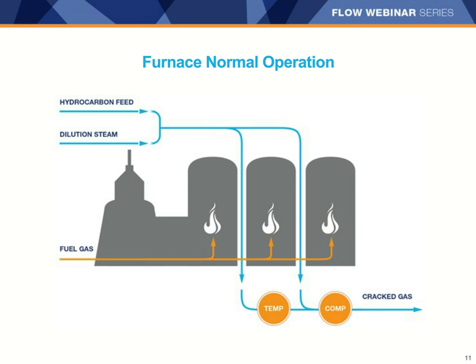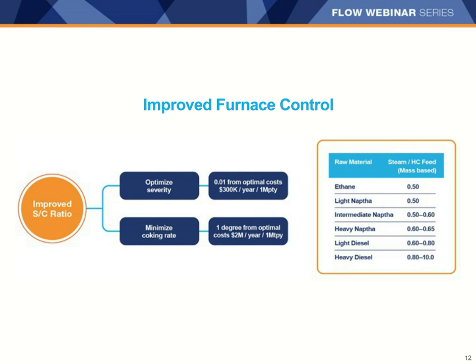In order to do this, the steam to hydrocarbon ratio must be very carefully controlled. Steam is added to reduce the temperature for the cracking and to help prevent rapid coking. However, if there's too much steam, it lowers the energy efficiency and the productivity. When there's too much steam, it also requires excess quench reagent, diminishes the amount of hydrocarbon that can be carried through the pipelines, and leads to higher velocities and more pressure loss. Every hydrocarbon feed has an ideal steam to hydrocarbon ratio, and being off from the optimal ratio by as little as 0.01 can cost $300,000 a year in lost yield for every million tons per year capacity.